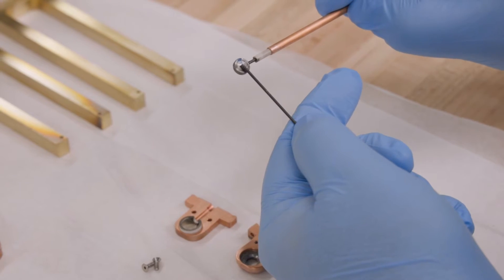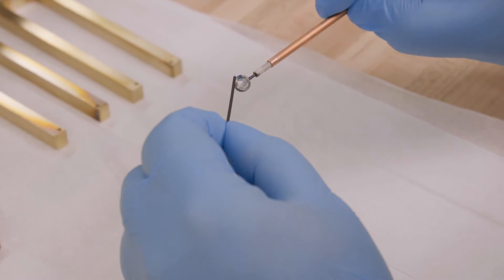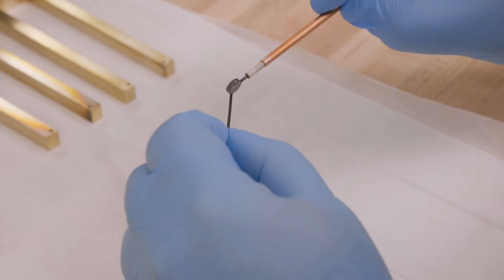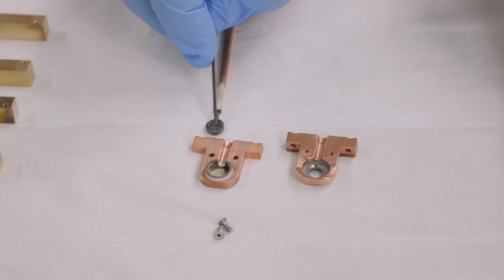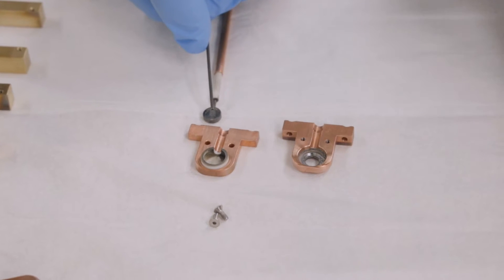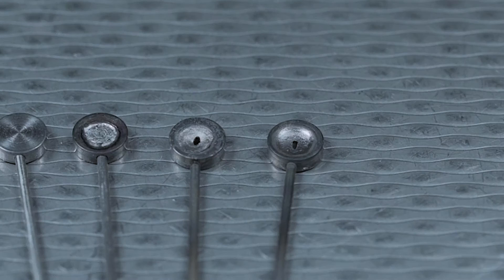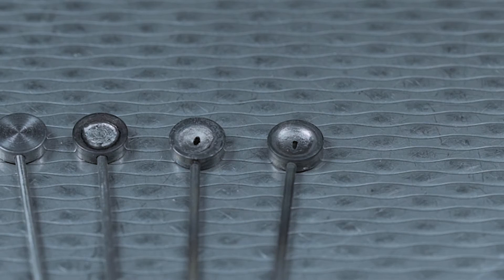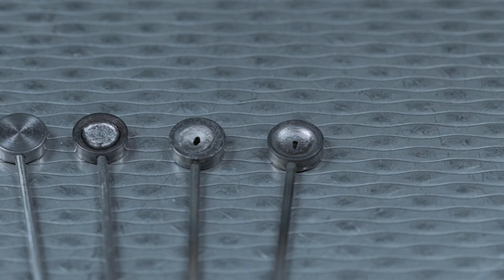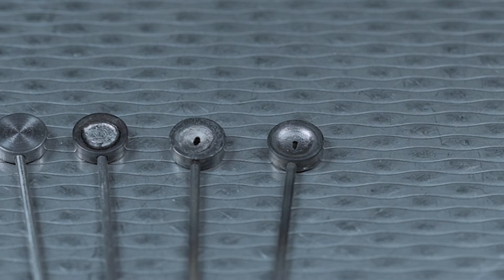Upon inspection, we see that these still have a little bit of life left in them. From left to right, we can compare an unused, a partially used, and two heavily used cathodes which have had substantial erosion to the point of exposing the counter bore for the electrical lead.